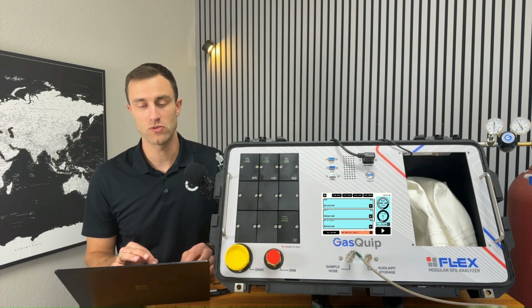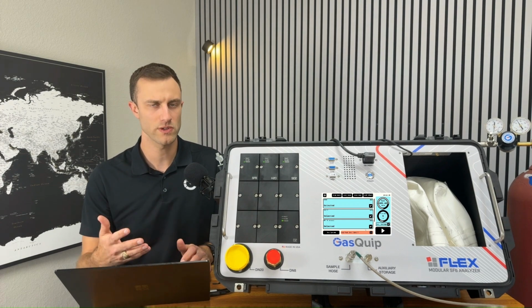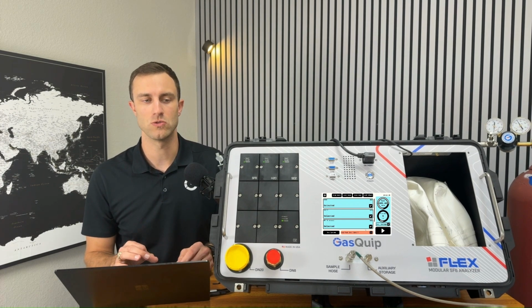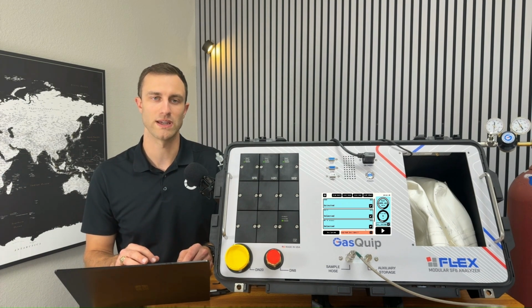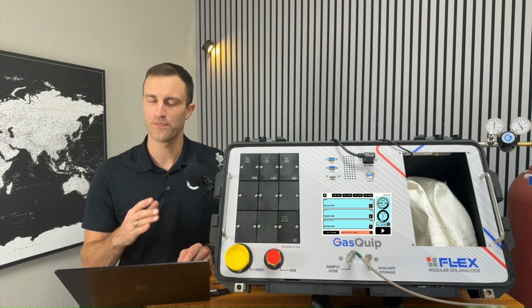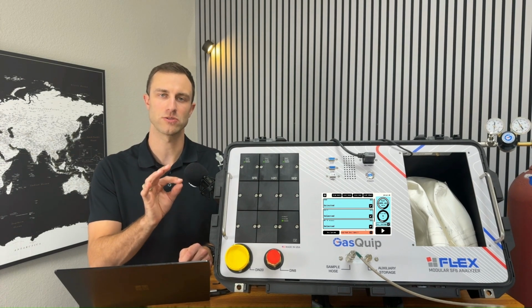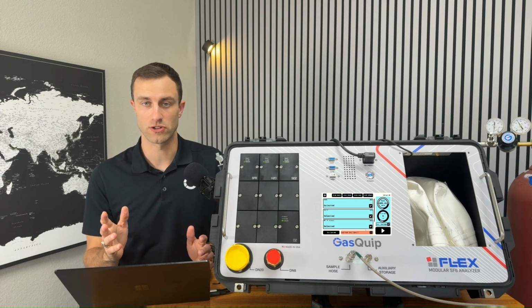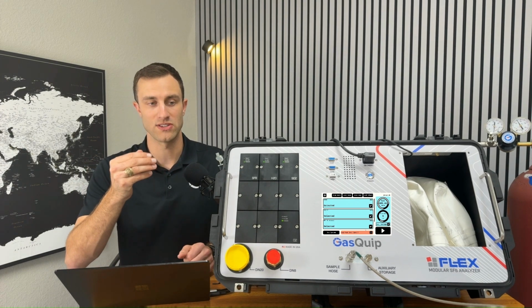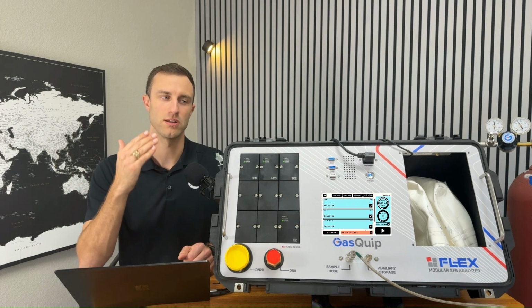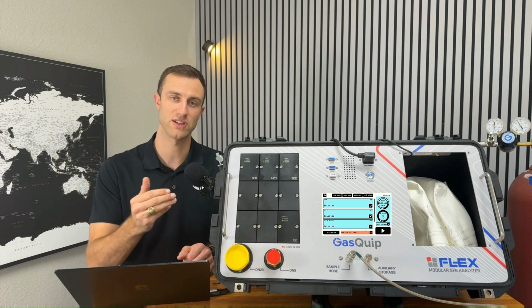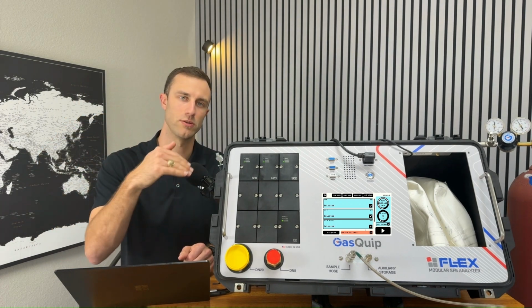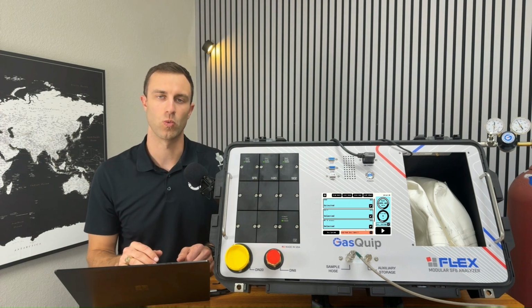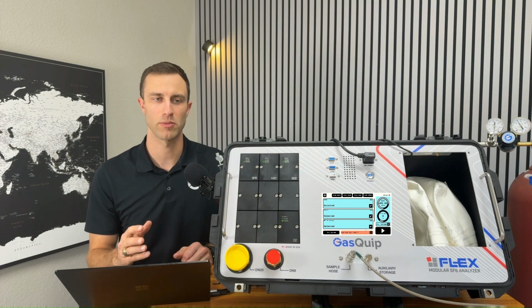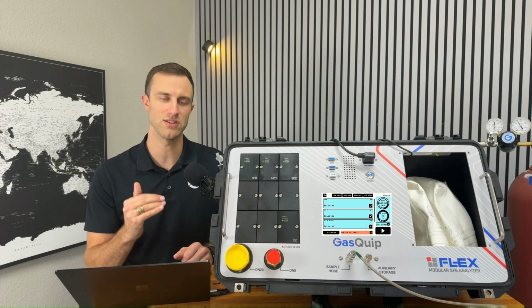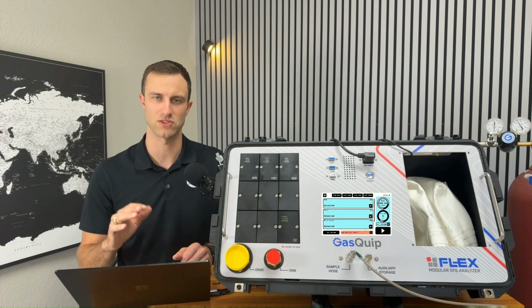If you do have SO2 that is showing a higher result than you expect, this could be because you tested sulfur dioxide at some point and it got stuck to the tip of the sensor. SO2 is very sticky and tends to hang out in the plumbing and on the sensor tips. It's just the nature of the beast. So what I would do is run a system flush, basically running a test on nitrogen. If you don't have nitrogen, you can use pure SF6 to flush out all of the individual piping and modules with really dry, clean gas. Probably run 3 to 4 tests with that and then see if you still are getting a reading of SO2 that you're not expecting to see.